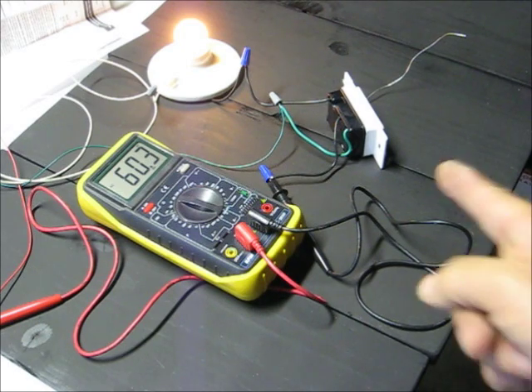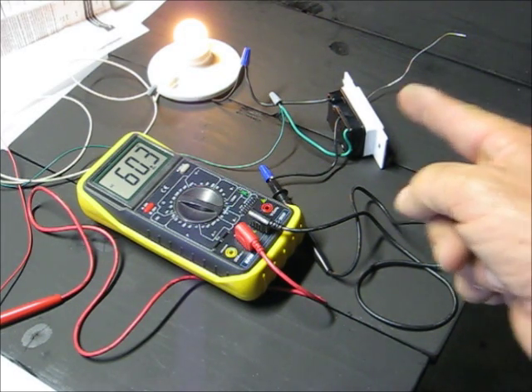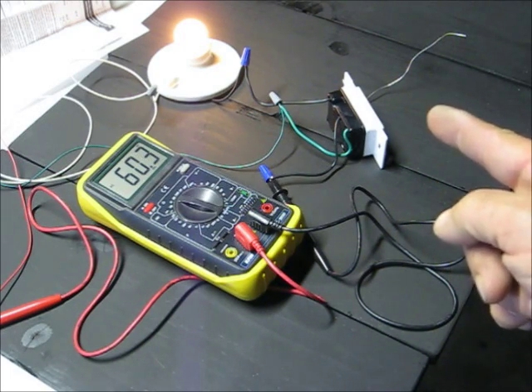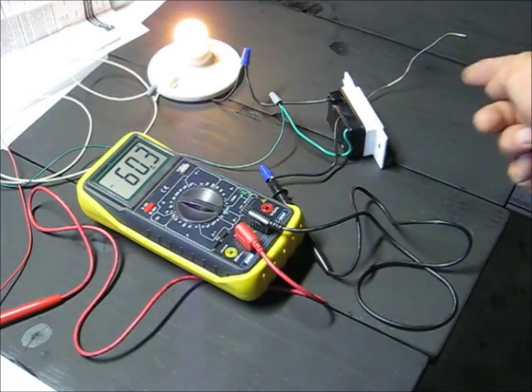Vacancy sensors have to remain auto on for 15 to 30 seconds after shutoff in case you're still in the room so you don't have to go back and find the button to push on it. It's called a grace period, and it's part of its Title 20 requirements.